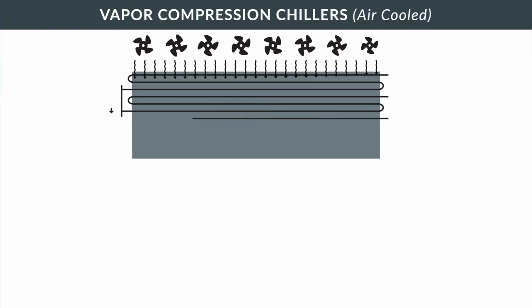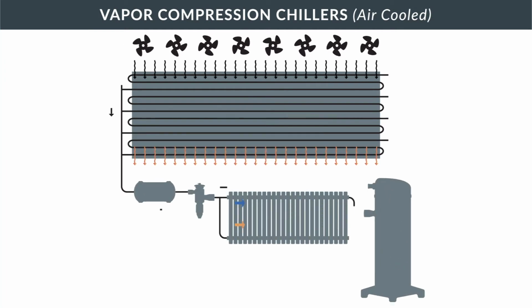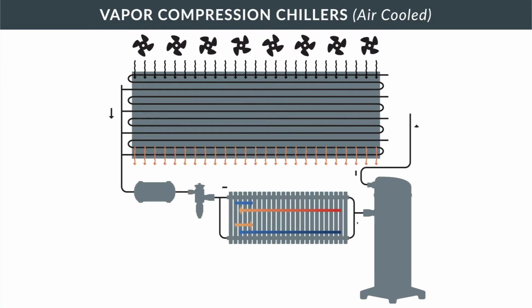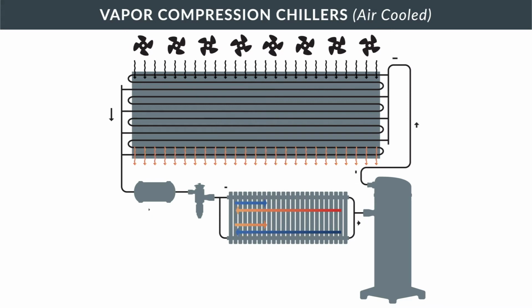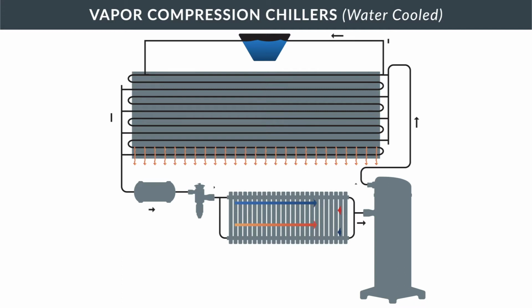The primary difference between air and water-cooled chillers is how the unwanted heat is rejected. Air-cooled chillers use air to remove heat. Water-cooled chillers use water or process fluid to remove heat. Apart from the fan and the cooling tower, the components between an air-cooled and water-cooled chiller are the same.